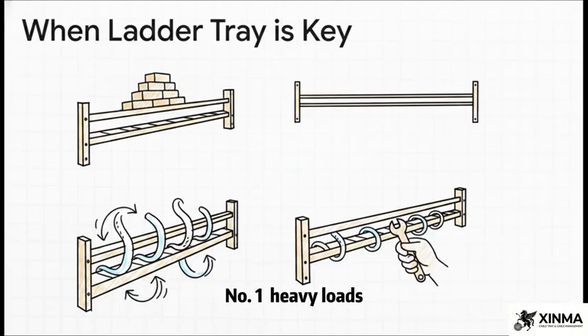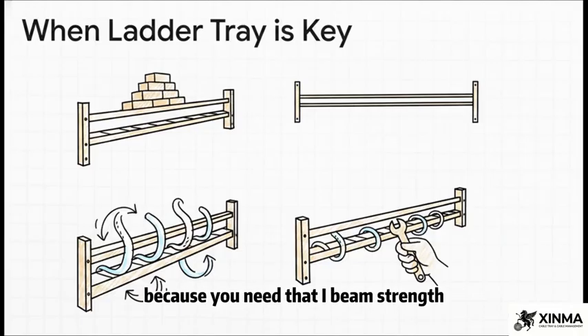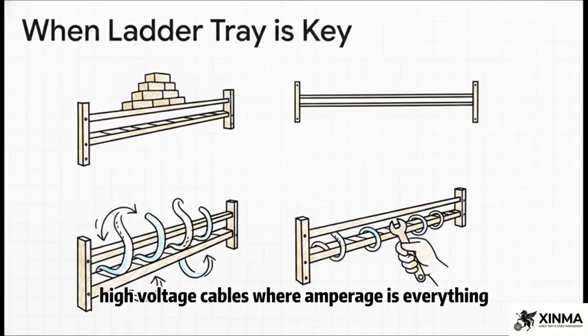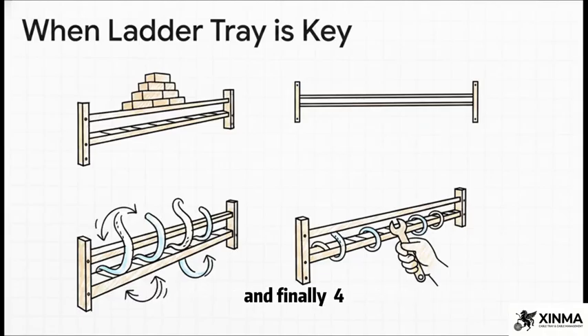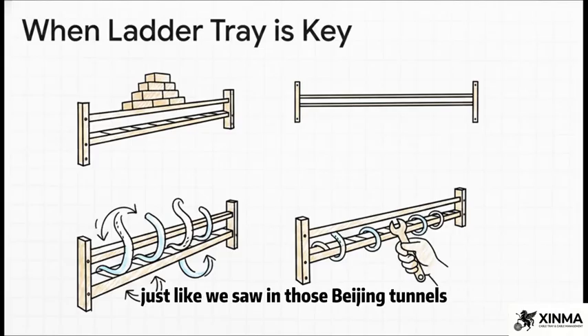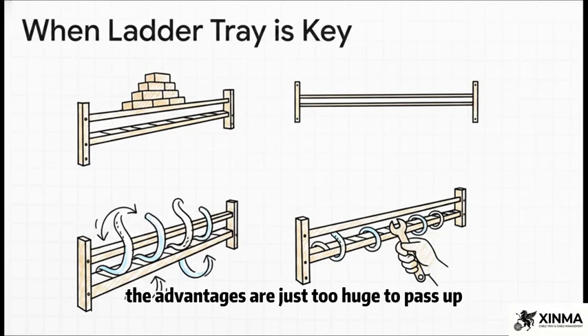When is the ladder tray absolutely non-negotiable? Number one, heavy loads, think Chengdu Metro. Two, long spans between supports, because you need that I-beam strength. Three, you need airflow, those hot, high-voltage cables where ampacity is everything. And finally, four, ease of access, just like we saw in those Beijing tunnels. If you've got any of these, the advantages are just too huge to pass up.